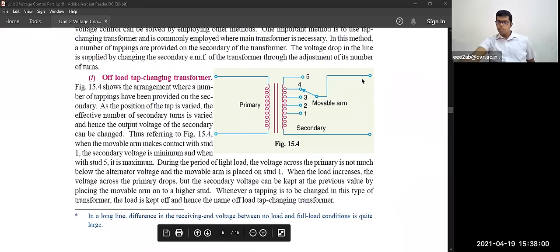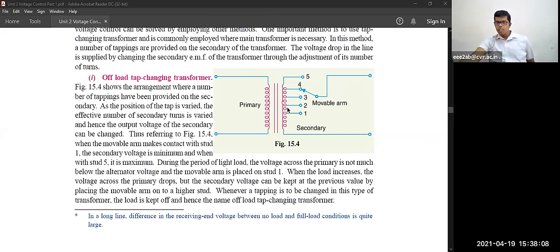So what you have to do is, one feeder will be there. You have to open this feeder, then only you have to come here and operate these tappings, whether you have to change to maximum or minimum. So that's how you change the tappings. By that time, your load should be kept off.